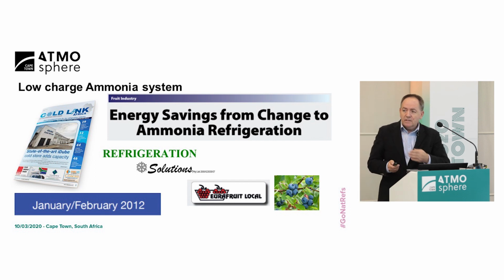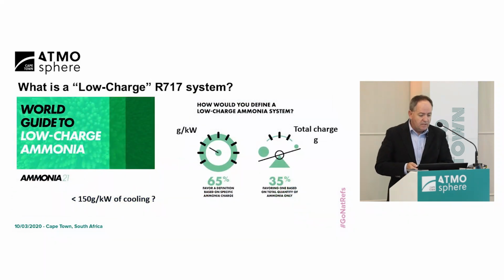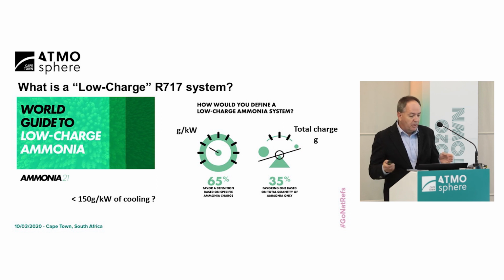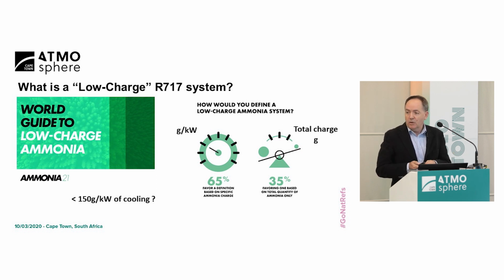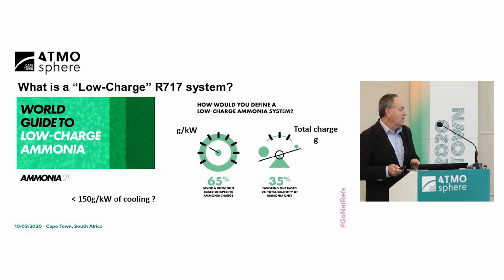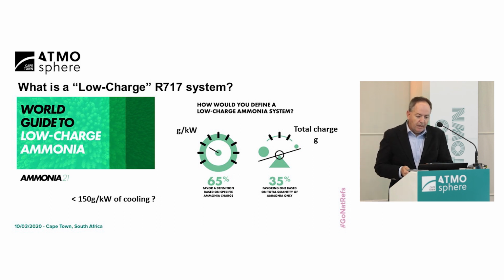Okay, so more recently, you had a publication on low charge ammonia systems. We certainly attempted to have the charge in that case as low as possible for many reasons, but primarily, of course, the toxicity of ammonia is a concern. So we needed to keep the charge very low, although low charge ammonia systems, that wasn't really a buzzword at the time. More recently, from your document, what defines it?